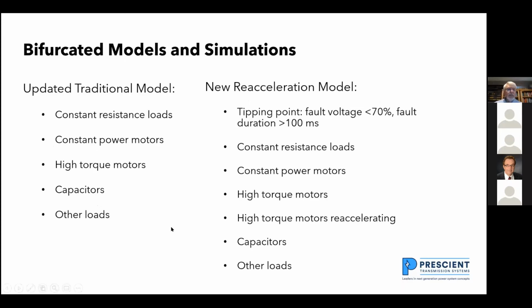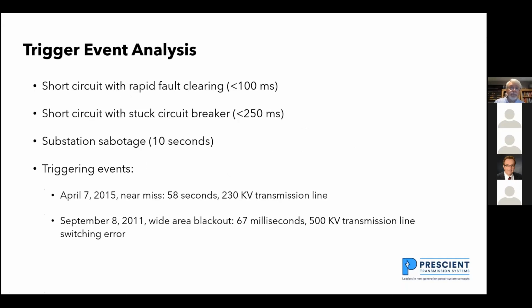If I look at the simulations, the traditional models I have show constant resistance loads, constant power motors, high torque motors, capacitors, and other loads. For the reacceleration model, you have to add this new line, high torque motors reaccelerating. The tipping point from the traditional model to the reacceleration model is this: if the fault voltage decays to less than 70% in an area, you're going to a reacceleration model. And if the duration is greater than 100 milliseconds, you've got to go to the reacceleration model.